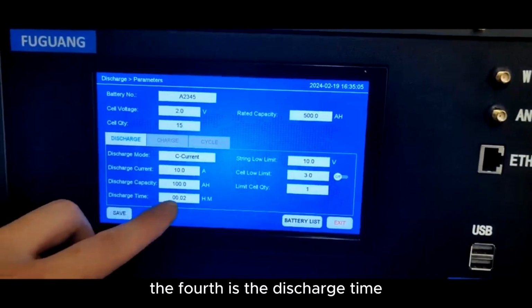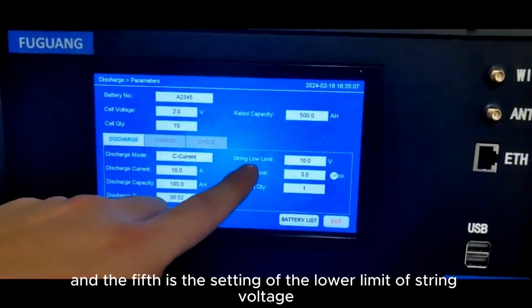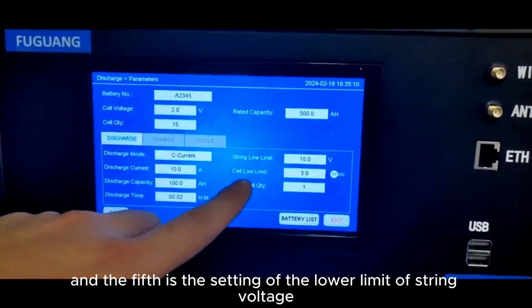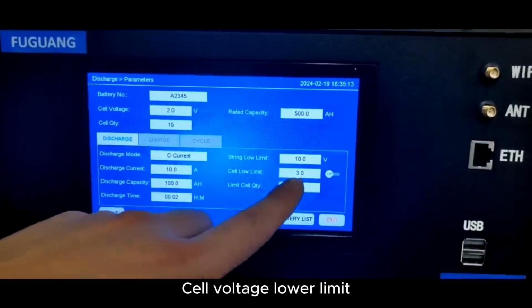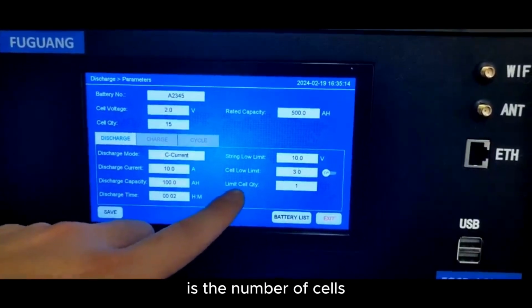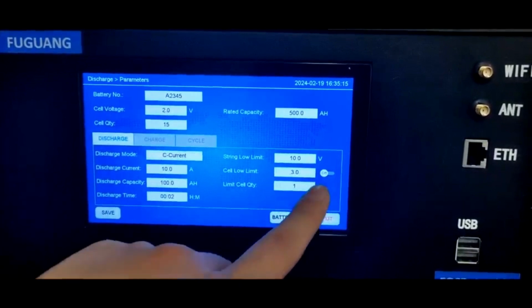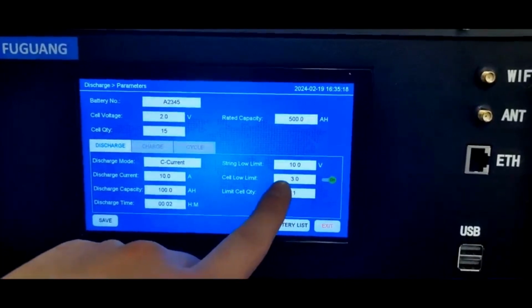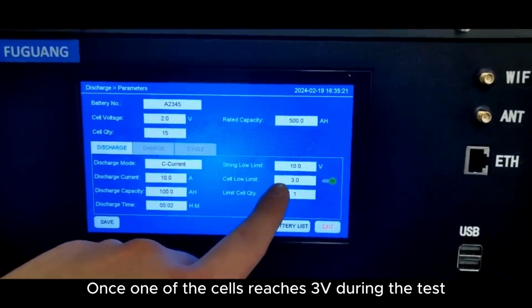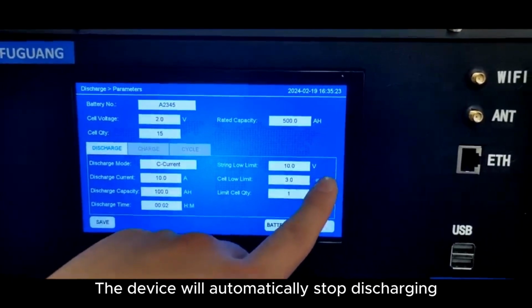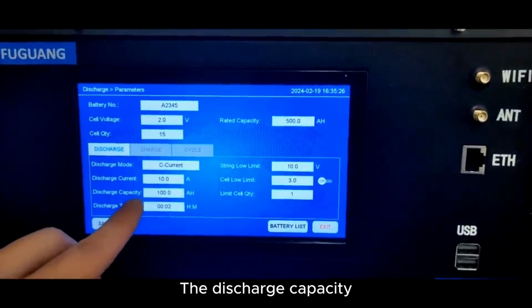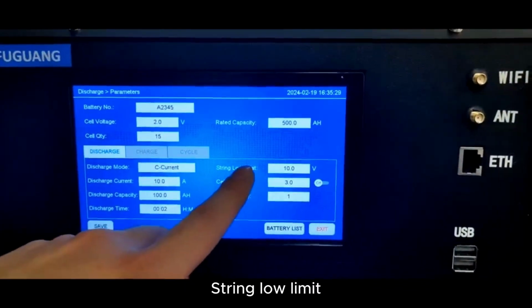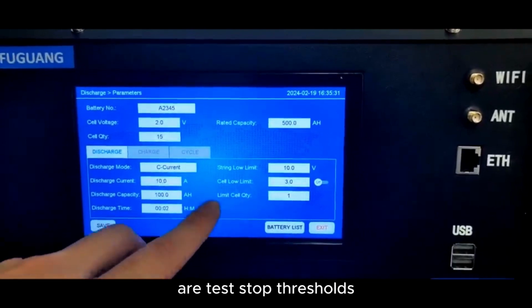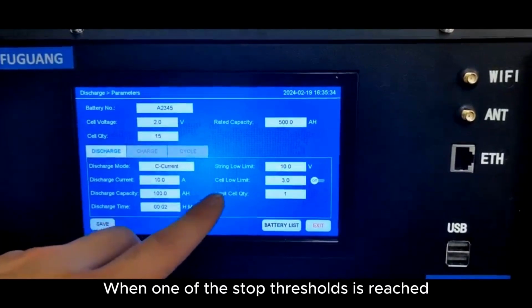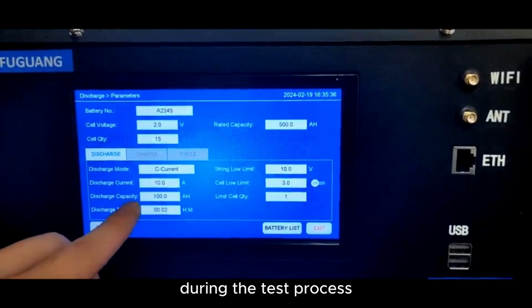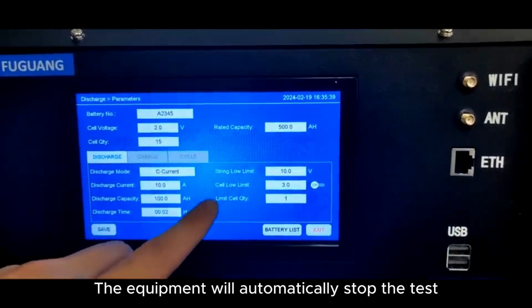The fourth is the discharge time, and the fifth is the setting of the lower limit of string voltage. The sixth is the setting of cell voltage lower limit. The seventh is the number of cells reaching the cell low limit. After turning on the switch, once one of the cells reaches 3 volts during the test, the device will automatically stop discharging. The discharge capacity, discharge time, string low limit, and cell low limit are test stop thresholds. When one of the stop thresholds is reached during the test process, the equipment will automatically stop the test.